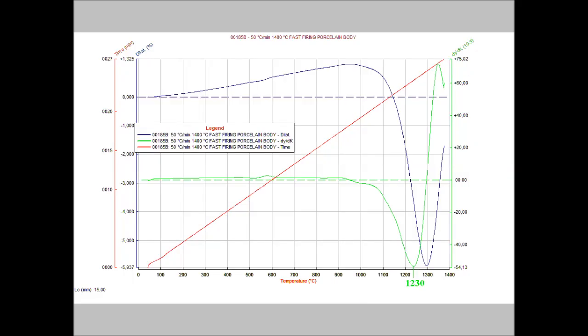One of the most interesting applications of the sintering curves is the possibility to identify the optimal temperature to reach the complete sintering in the shortest time, avoiding the risk of overfiring and bloating the material. Running a test with constant heating rate up to bloating, it is possible to identify the temperature of maximum sintering rate. This temperature is identified by the negative peak of the first derivative of the sintering, or the sintering speed, which is the green curve. In this case, it is 1230 degrees.